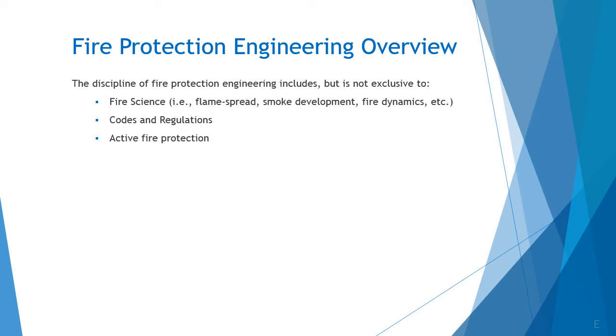You have active fire protection systems, like sprinklers and alarms, anything that moves or makes noise. You also have passive fire protection, which is very important too, such as compartmentation of spaces so a fire stays contained to a location. That includes separations of major areas of buildings, firewalls, and fire dampers, which maintain and keep smoke and fire from spreading from point A to point B, allowing occupants to remain safe.